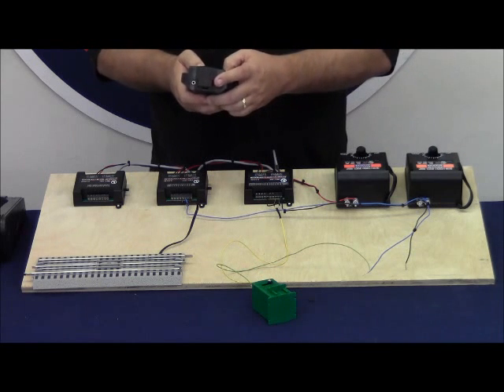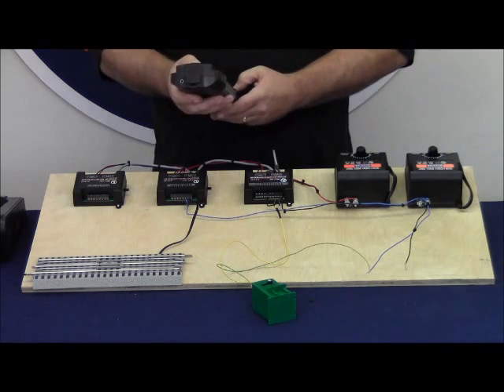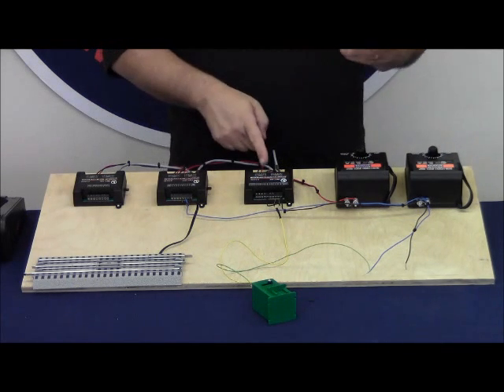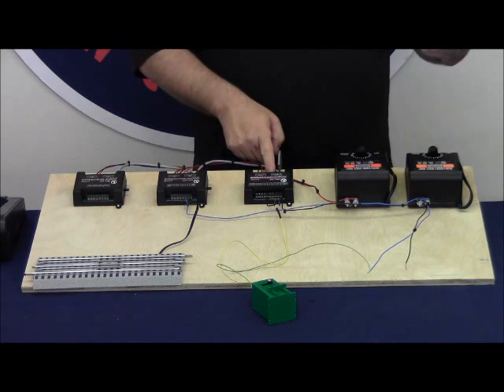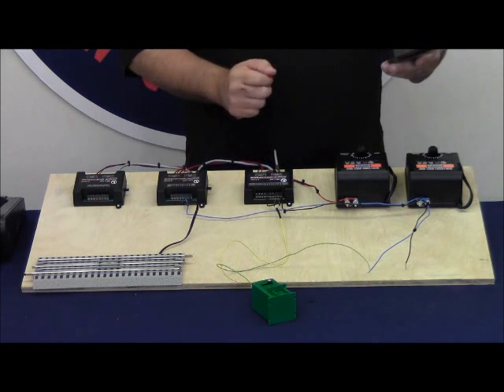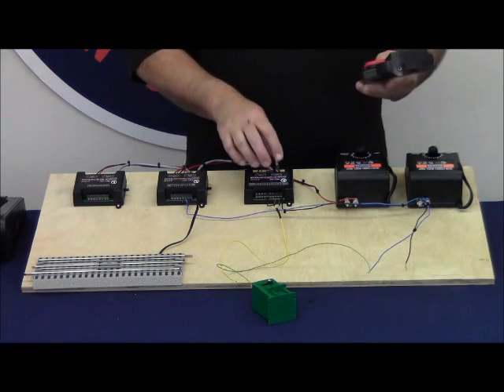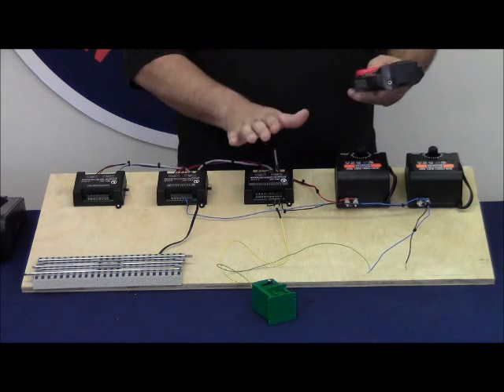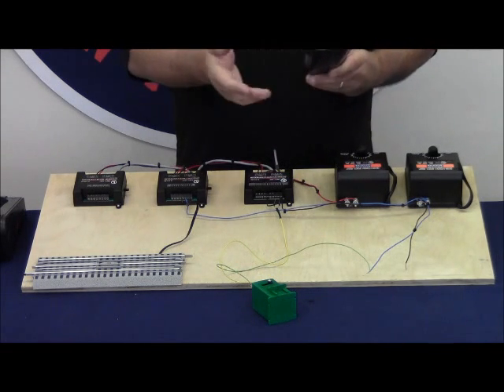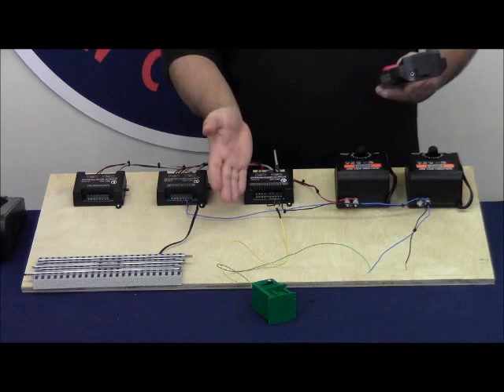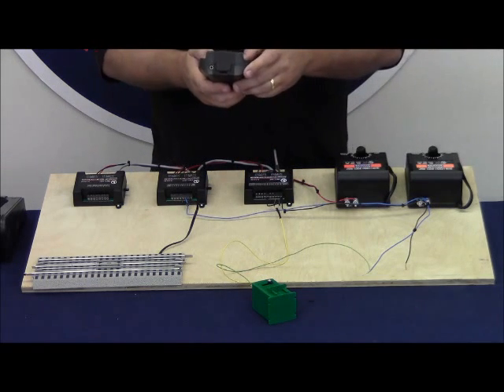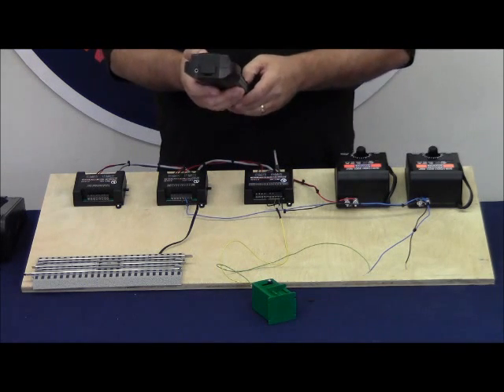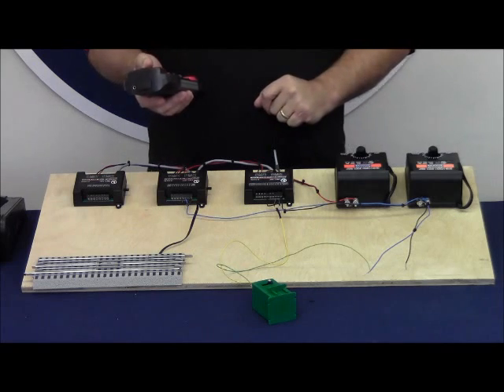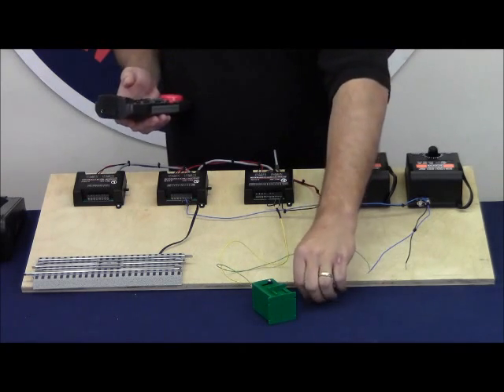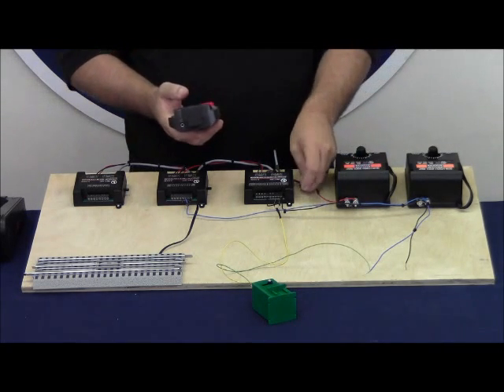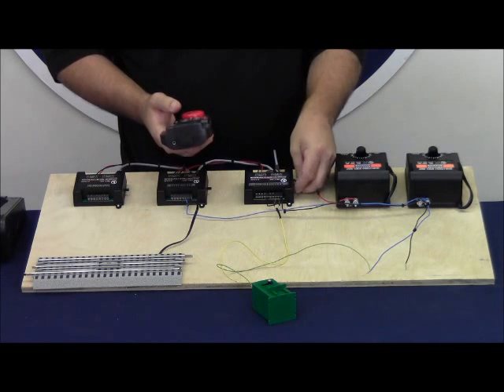So I press 99 set. You may not be able to see it, but my green LED comes on when I press the set button—I've now told my ASC that it's going to provide constant voltage. I then need to program my switch outputs 1 through 4, so I press switch 1 set. My green LED comes on again. I can replace my jumper because the programming is completed.